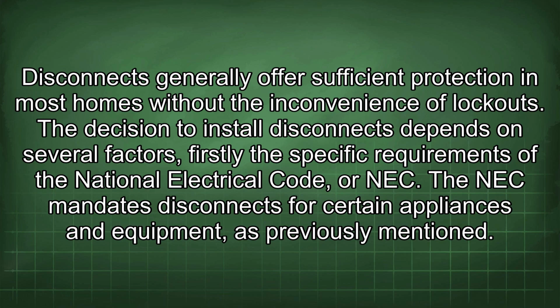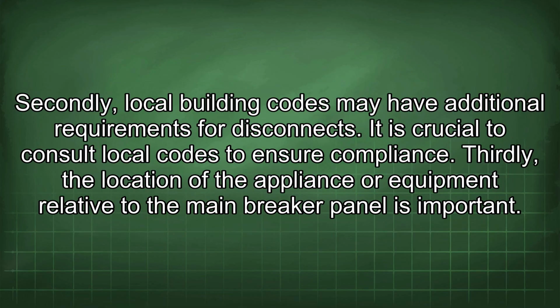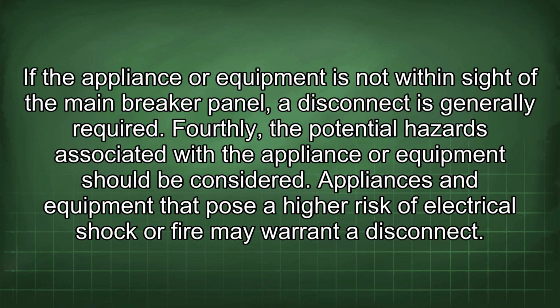Firstly, the specific requirements of the National Electrical Code, or NEC. The NEC mandates disconnects for certain appliances and equipment, as previously mentioned. Secondly, local building codes may have additional requirements for disconnects. It is crucial to consult local codes to ensure compliance. Thirdly, the location of the appliance or equipment relative to the main breaker panel is important. If the appliance or equipment is not within sight of the main breaker panel, a disconnect is generally required.